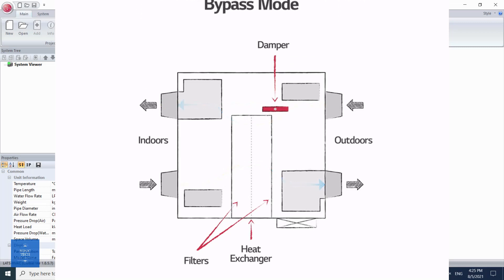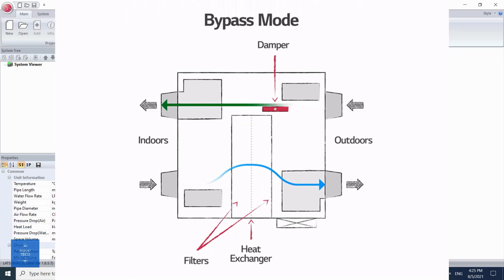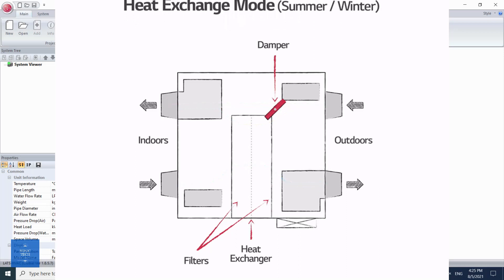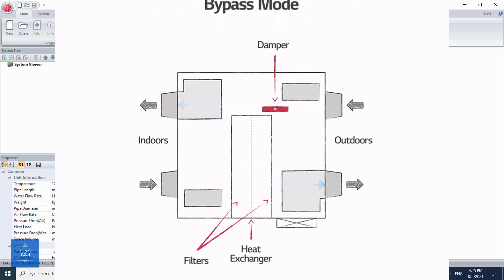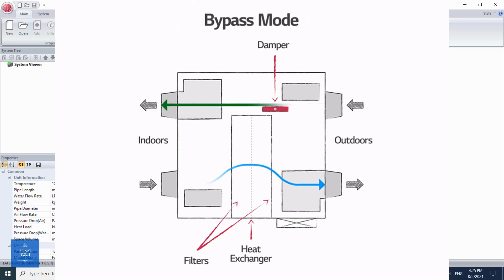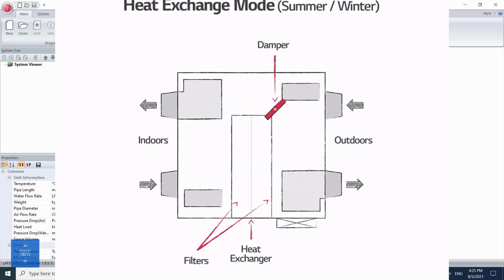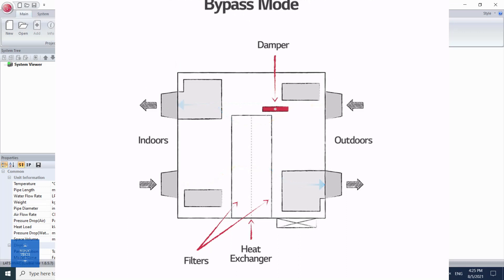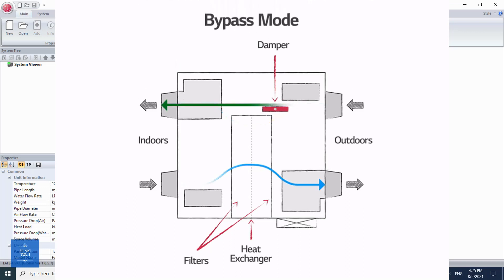Since every device is limited by the laws of thermodynamics, an ERV system cannot achieve 100% energy recovery. The effectiveness of ERV units is certified by AHRI, and it changes based on environmental conditions. Performance is normally defined separately for summer conditions and winter conditions.